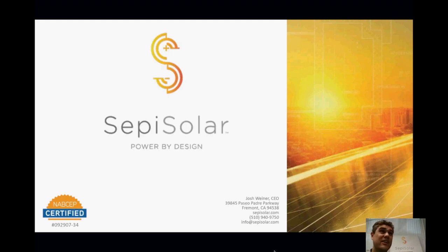Where it gets even more interesting is line side points of connection. Not to go off on a tangent, but I will. For 705.12, the 120% rule, you treat it similar to a solar system. You add up the current supplied, the maximum discharge current that can be supplied from the battery, and add it to the solar. So now you've got the sum of both, and that sum cannot exceed 120% of the rating of the bus bars or conductors they're attaching into, and everything upstream from there as well.